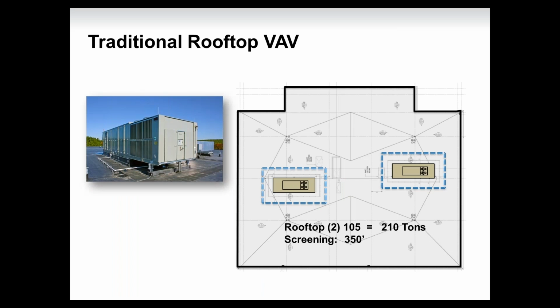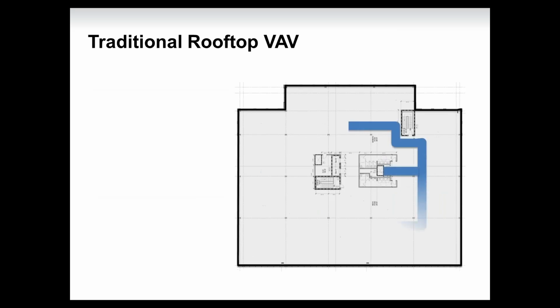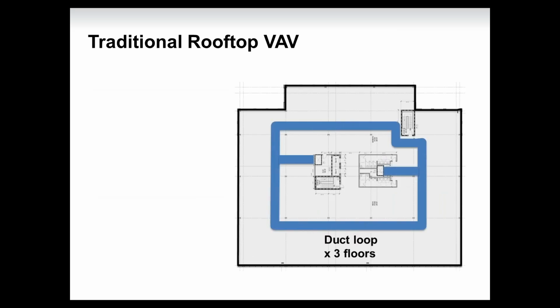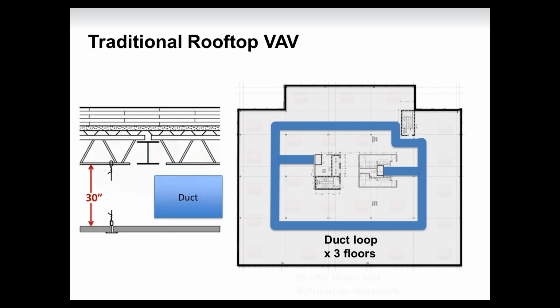So as I stated earlier, the other costs for rooftop units would be the screening. So for the rooftop design for this building, two 105-ton rooftops, 210 tons of cooling, will require 350 lineal feet of rooftop screening. Additionally, on each floor, we have to provide a duct loop from those units. The duct loop will require the plenum space to be approximately 30 inches high, not only to allow for the ductwork, but to allow for the other systems such as fire protection that would go in the ceiling plenum space.